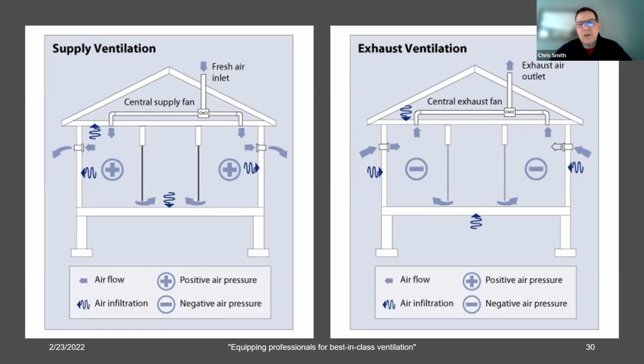Exhaust ventilation is very similar, except instead of forcing outdoor air into the building, you're forcing the indoor air out of the building. And so instead of positively pressurizing the house, now you're negatively pressurizing the house. When you do that, you're not driving exfiltration, but instead you're creating a vacuum and you're driving infiltration. Again, if you're using an exhaust fan and negatively pressurizing the house, that vacuum could pull outdoor air in through open windows or vents. But again, most likely it's pulling it in most of the year through cracks in the building envelope. And so you're experiencing infiltration.